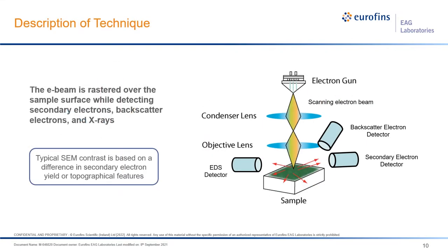We can take advantage of these simultaneous processes, and with the proper detectors, provide ourselves with multiple distinct images of the near-surface region. In the SEM, by flipping a switch, we can acquire three different images: the secondary electron image, the backscatter electron image, and a fluorescent or characteristic x-ray image using the EDX detector. Few analytical tools provide the dexterity in acquiring data that a modern SEM can provide.